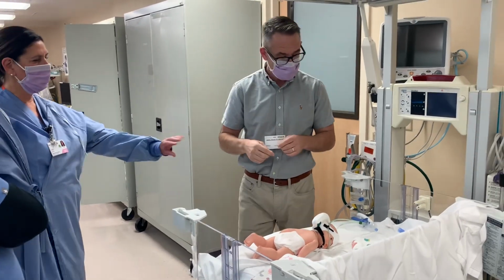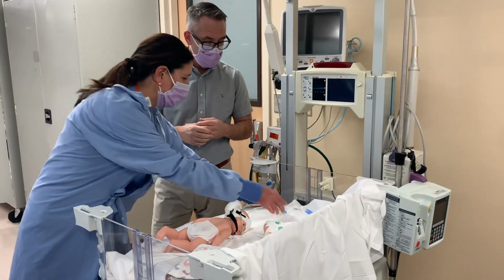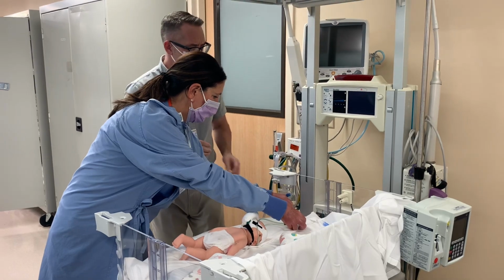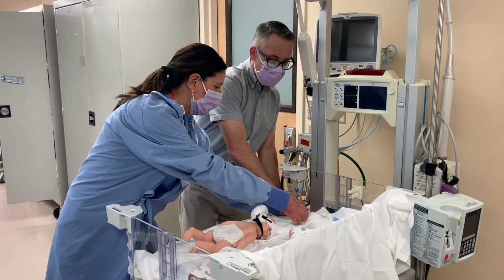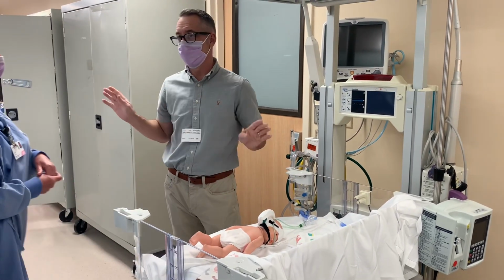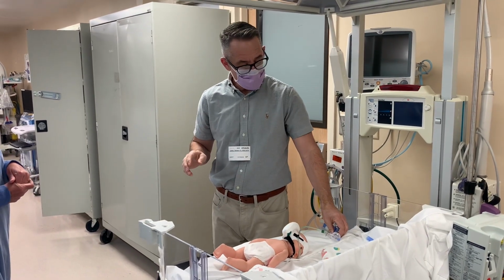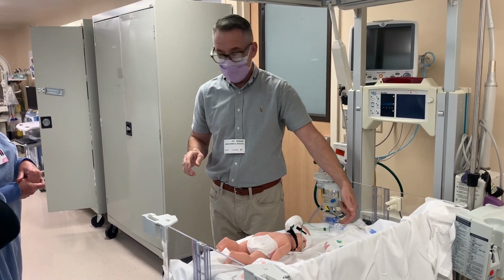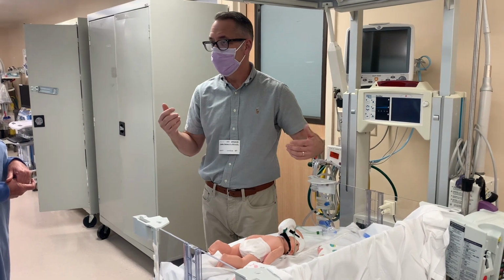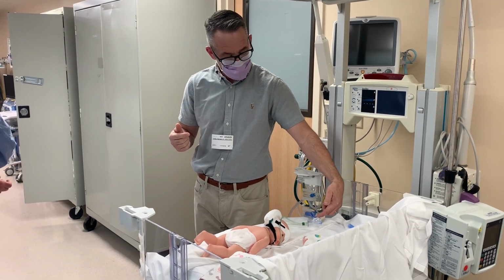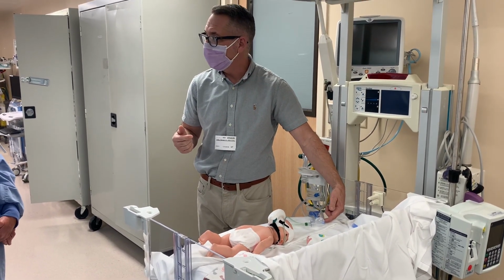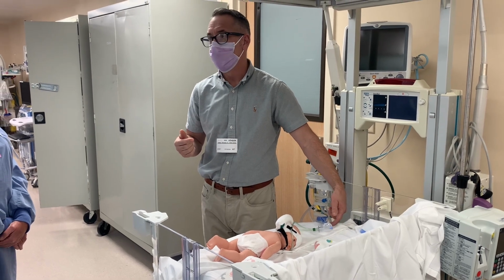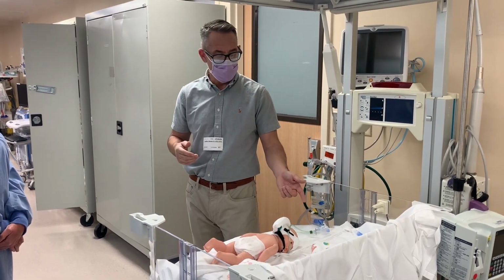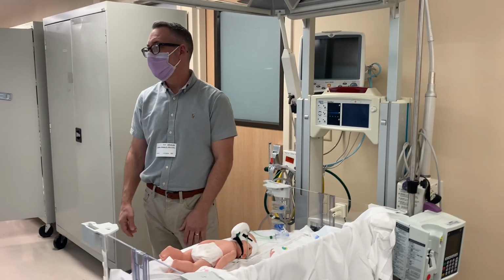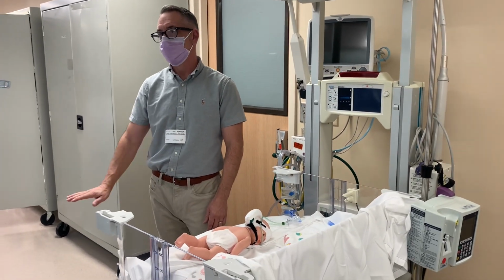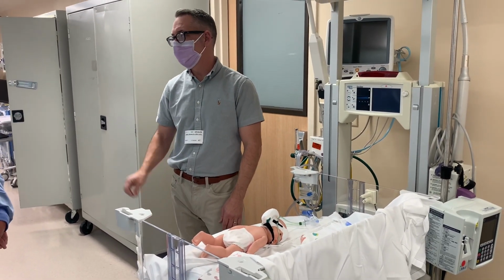Yeah, does the blue actually have to be on top, because we put that a lot, or it needs to be? It used to be that way. Well, therapeutically, it doesn't make any difference. I mean, for the rainout. But for the rainout, if you wanted to come out through the expiratory limb, by just simply the physics, heavy water coming in this way, you'd want it on top so that as it's wicking out, you want it to drain below. Whenever I do training on my CPAP devices, I always put the expiratory limb below, and that seems to help with rainout to a degree.